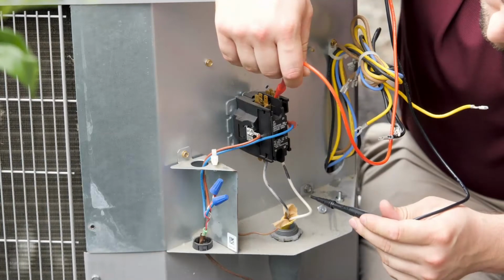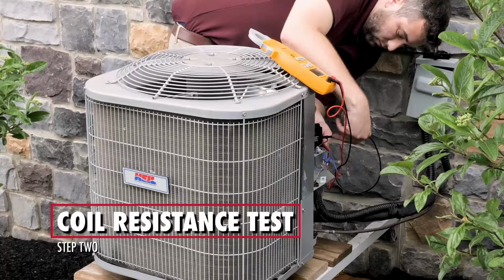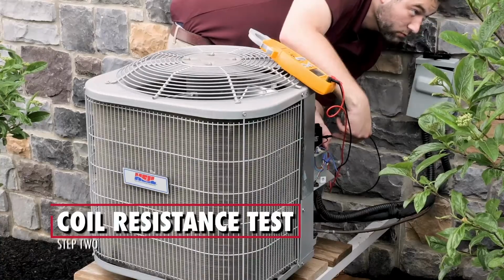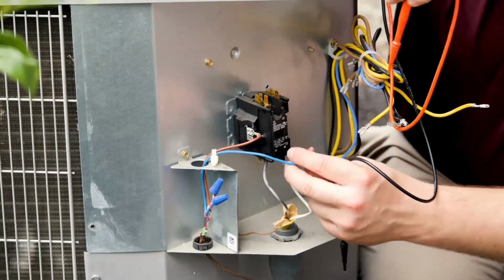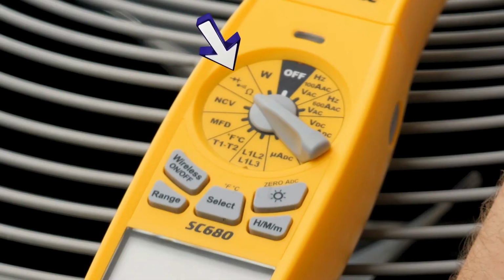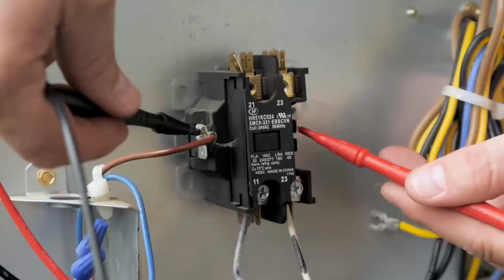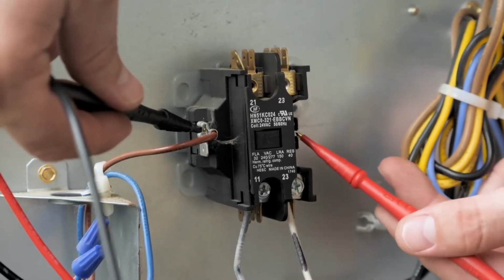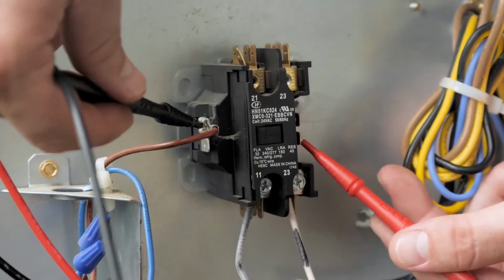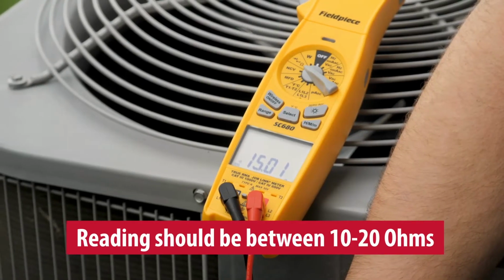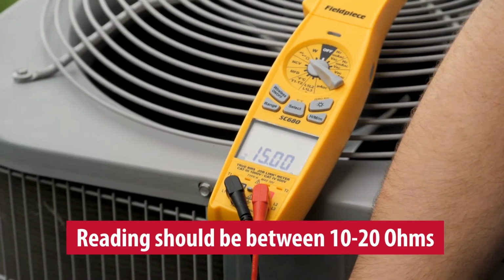If the contactor had not closed, we can verify the condition of the coil using a resistance test. First, remove the blue control wire. We'll set our meter to ohms, which is resistance, and we'll place one lead on each side of the contactor coil. We should see between 10 and 20 ohms resistance through the coil.